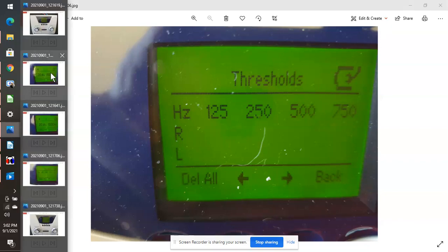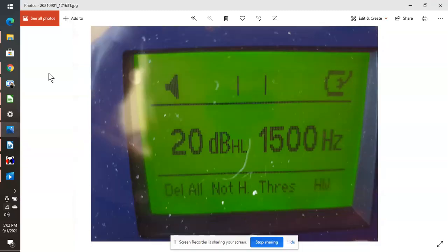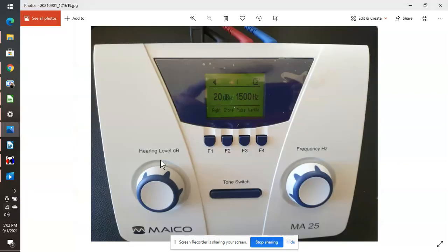And look, the thing with hearing testing is the best way to actually do a hearing test is to put the headphones on yourself, grab the patient response button, and turn the controls on the audiometer, and just get a feel for it. Increase the volume up and down, change the frequency, push the tone on so that you can hear when the tone comes on, you can see what happens on the display, push the patient response button, and you'll see what happens on the display. Change the ears from right to left, backwards and forwards, hit the pulse and warble tone.